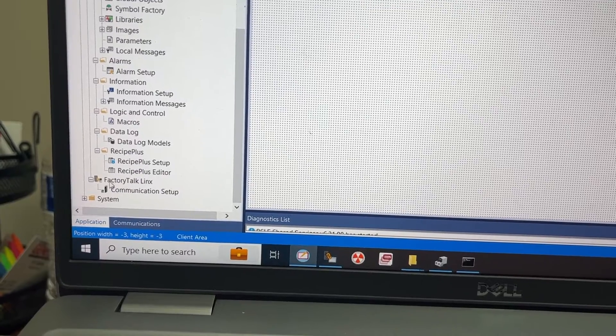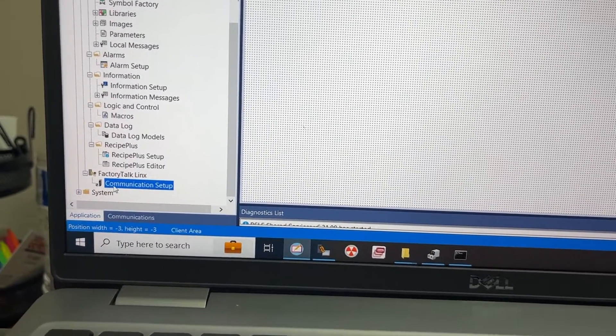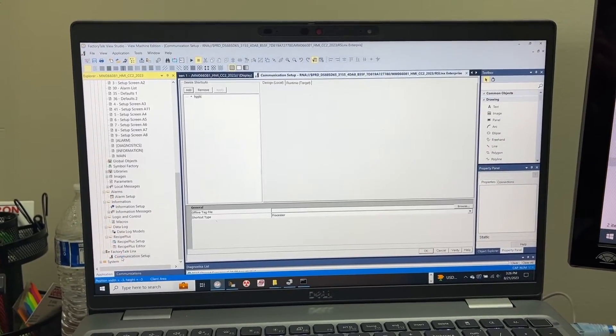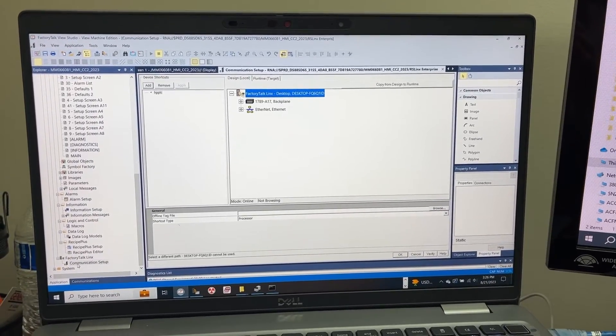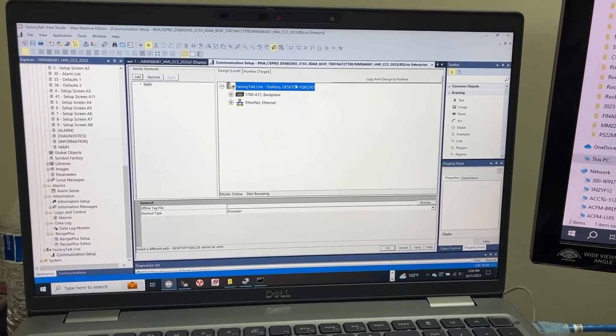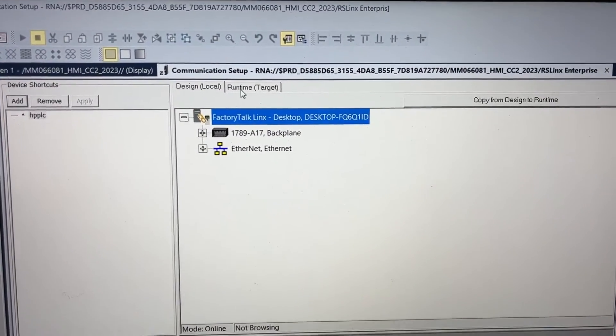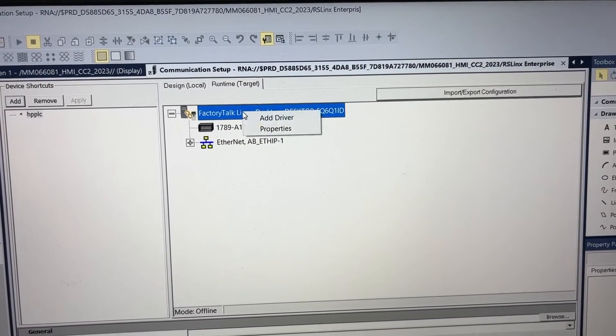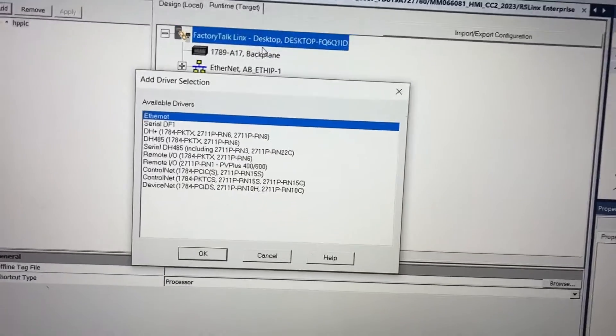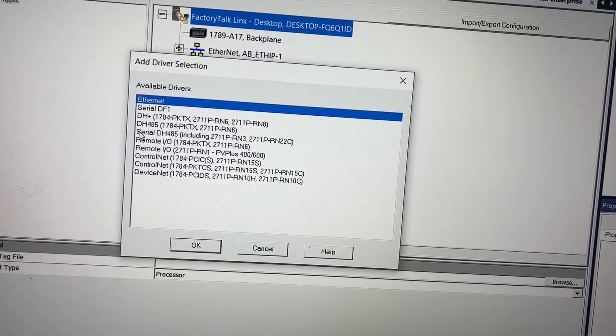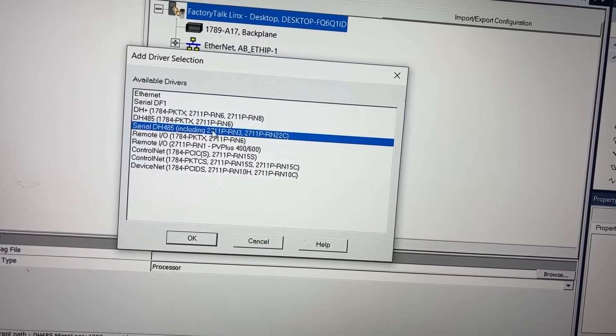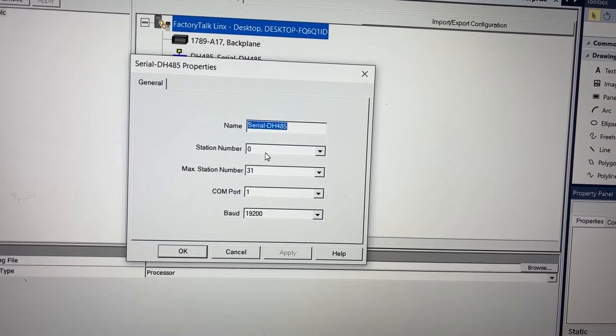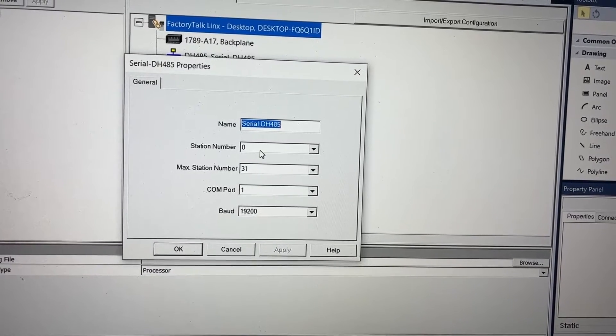Under FactoryTalk Linx, go to Communication Setup, then go to Runtime Target. Right-click on FactoryTalk Linx, add driver. Select Serial DH485. Station number 0 is the node number for the first HMI.